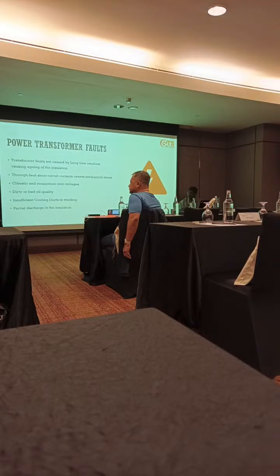So we will always use the on-load tap changer or the off-load tap changer on the HV side, not on the LV side. Why? Because the HV is easy to access. If we turn one winding or one turn, it will have a smooth replica, and small fine tuning of the LV voltage can be done using HV. This is the one thing. And also on the HV side, the current will be less when compared to the LV side. So the arcing or other phenomena will be avoided when the OLTC is installed on the HV side.